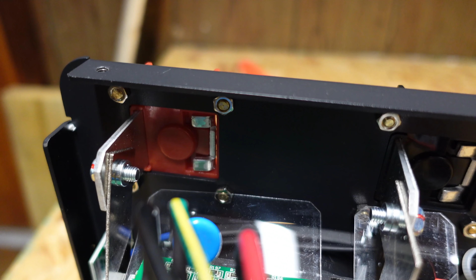One thing I was somewhat interested in is the backside of these terminals that I mentioned seem to be a little bit loose. It looks like they are designed that way. As you can see, there's no nut back there. The end of the screw is confined in this little plastic covering. So it is designed such that when you tighten that flange nut down, it pulls this tight.